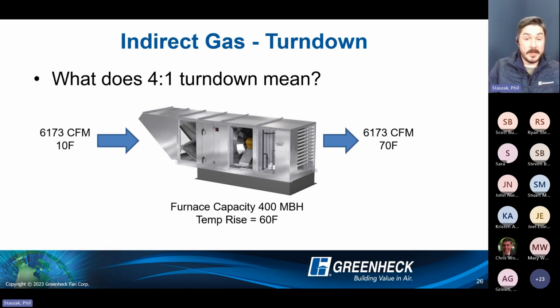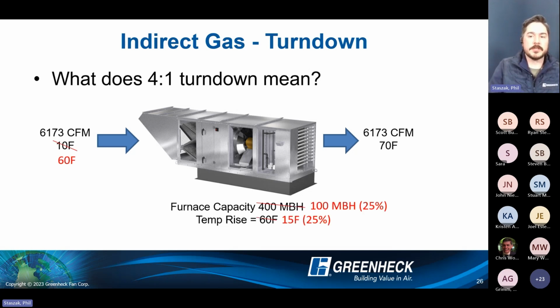Where this gets unique is we're getting into the season right now. We're finally, spring is here. So those outside air temperatures during the early hours and late hours may be a little cooler, but maybe you only need a 10 or 15 degree temperature rise. Well, what does 4-to-1 mean when you have a 60 degree design rise and you need to know your minimum? What if you have a 60 degree outdoor air condition and you still want to discharge 70 degrees? Well, with 4-to-1 turn down capacity, 60 degrees divided by 4 is 15 degrees. That's your minimum. So your minimum capacity is still overshooting your design discharge air temperature. So that furnace is going to cycle on and off on those shoulder days.